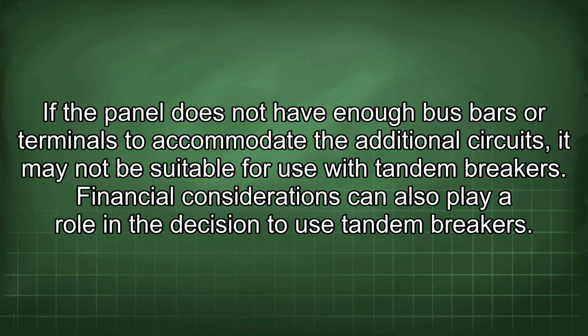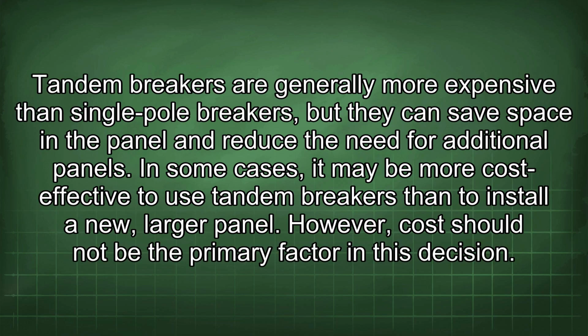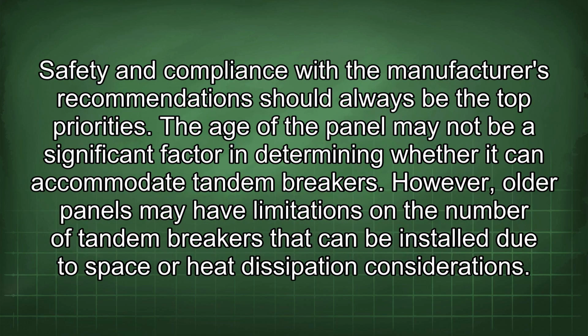Financial considerations can also play a role in the decision to use tandem breakers. Tandem breakers are generally more expensive than single-pole breakers, but they can save space in the panel and reduce the need for additional panels. In some cases, it may be more cost-effective to use tandem breakers than to install a new, larger panel. However, cost should not be the primary factor in this decision. Safety and compliance with the manufacturer's recommendations should always be the top priorities.